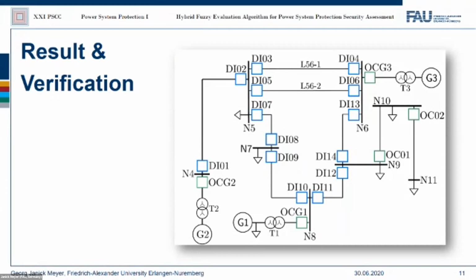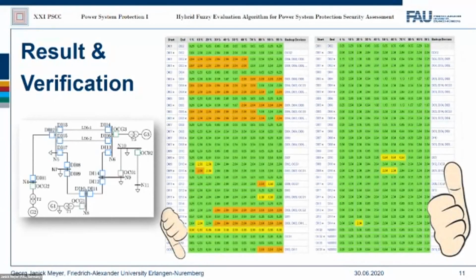To verify the effectiveness of our new hybrid evaluation and optimization strategy, we used the proven PSA method of the program PSS Sincal to evaluate the optimized settings and compare it to the evaluation of settings calculated by adjustment rules based on equipment data from equations of the literature. It can be clearly seen that the results of our new evaluation method on the right side perform significantly better. Almost all short circuits were cleared selectively, and just a few faults were cleared with an overfunction, but that concerns just the backup protection if primary protection fails.